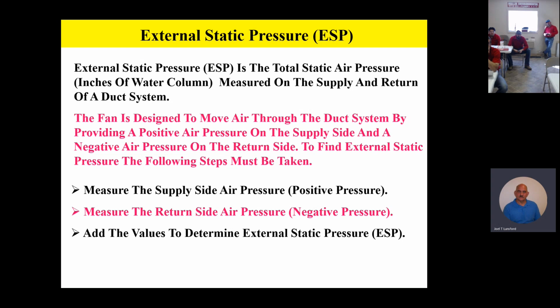So on the return side, you have to think about what components in the airstream the fan is going to be sucking against. What we're really looking at, external to the fan, is what it's blowing against and what it's sucking against. That's what external static pressure is. It's how much energy the fan is using to blow air down the supply and to suck air back on the return. That's what we're looking at when we're looking at ESP, also called external static pressure.